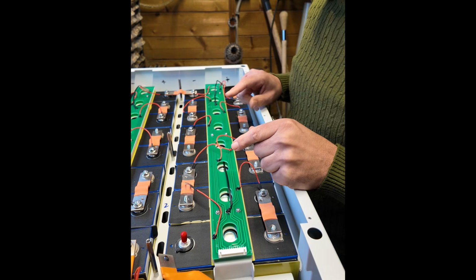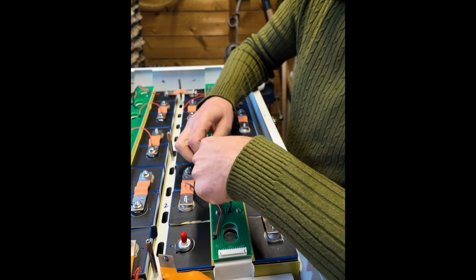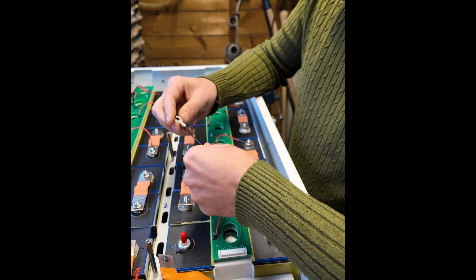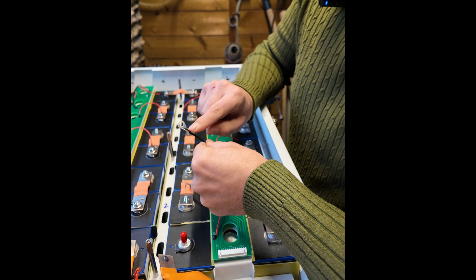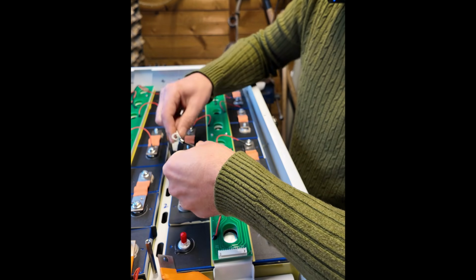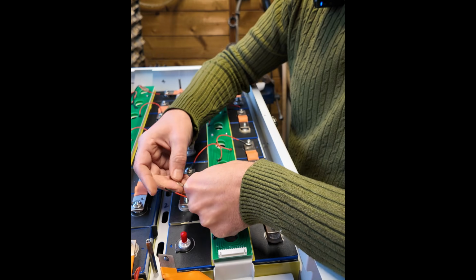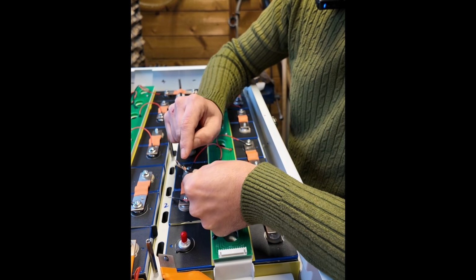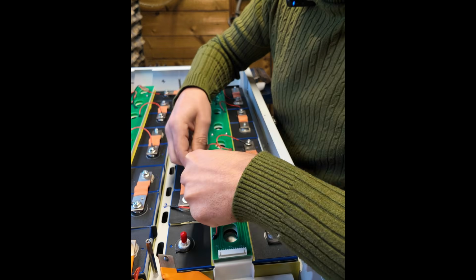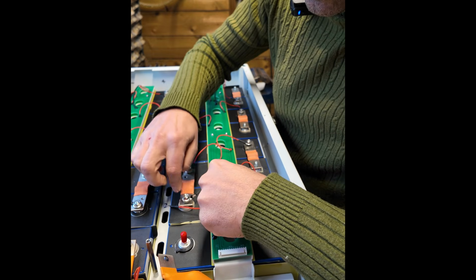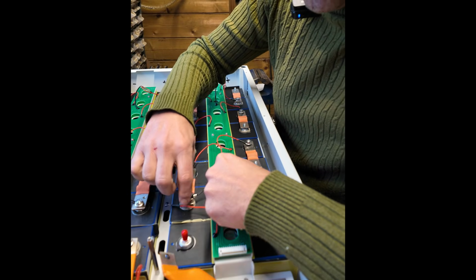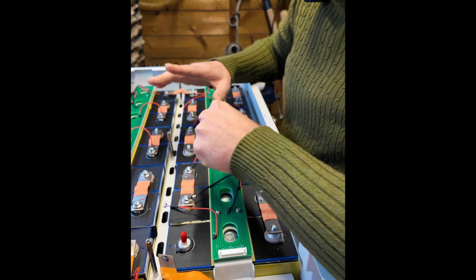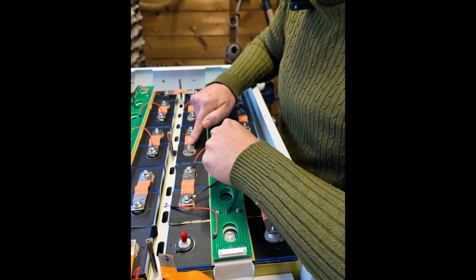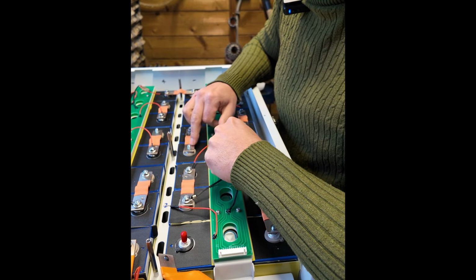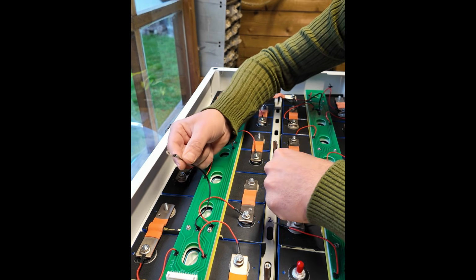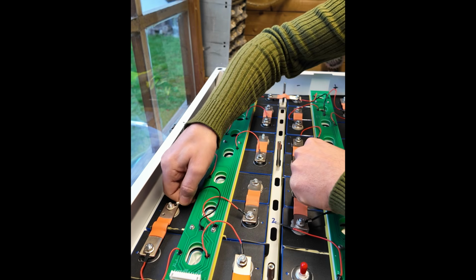Attached almost all balance wires. Now I check these temperature sensors. They're just glued into the connector, so it's best to mount them somewhere on a connector. This is completely isolated, so there's no risk of creating a short. Just connect them to a bus bar, and it will check the temperature of the bus bar. If there's a bad contact, we can always see if the temperature rises inside the box. There are 4 of these temperature sensors.